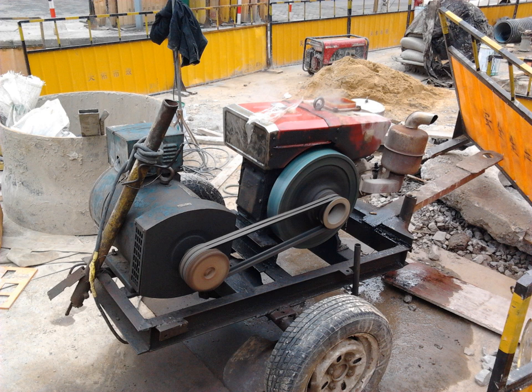Diesel generators are also used for emergencies or backup where either a redundant system is required or no generator is on site. To make the hookup faster and safer, a tie-in panel is frequently installed near the building switchgear that contains connectors such as cam locks. The tie-in panel may also contain a phase rotation indicator for three-phase systems and a circuit breaker.